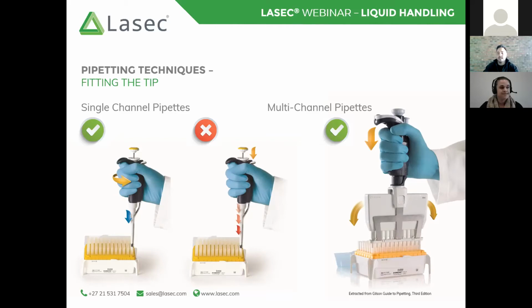In certain situations, especially in small volume pipettes, you'll find that those tip holders are very, very thin and therefore quite fragile. So before fitting that tip, just make sure that it lines up really nicely with that tip before applying the downward pressure. All you have to do is apply a slight downward pressure, and we just recommend a slight rotation. This should be sufficient to fit that tip. If you are finding that excessive force is required, consider trying a different tip. It may be that the tip that you are using just isn't right for that pipette, maybe it's an incorrect volume. Alternatively, it might just be a tip that's not compatible.